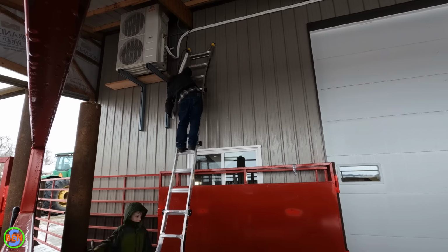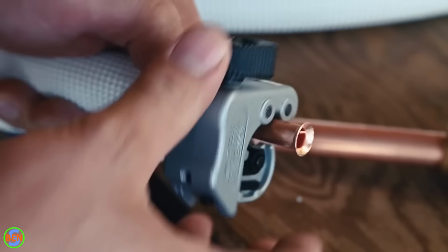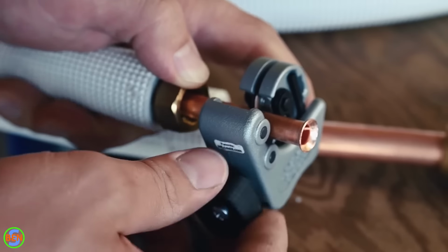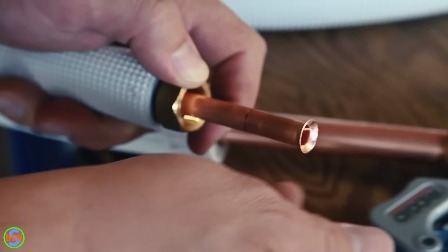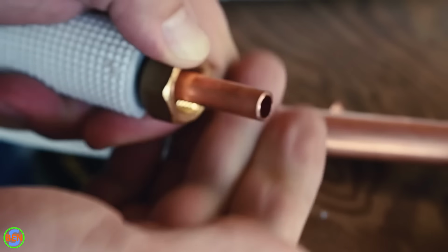If you inspect them and they look perfect, with no imperfections on the face of the flare where it's going to be coming into contact with that brass fitting, you might be good to go, but most of the time you're going to want to just cut them off and redo them. The slower you cut it, the less of a burr you're going to create inside of the tubing. So I'm just tightening it a little bit at a time. When you can feel it starting to get close, instead of cutting through the rest of the way, you can just push it to the side, like that.